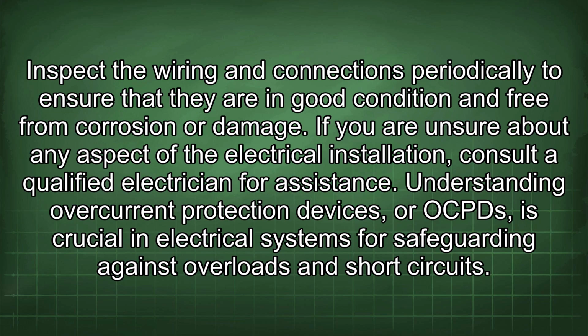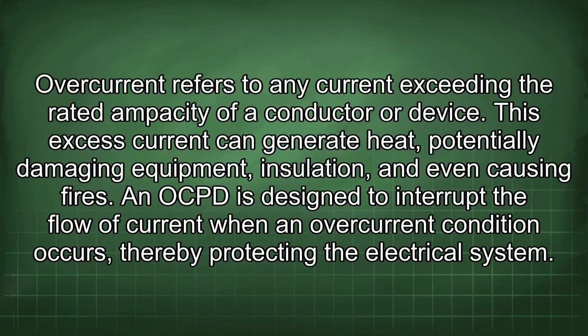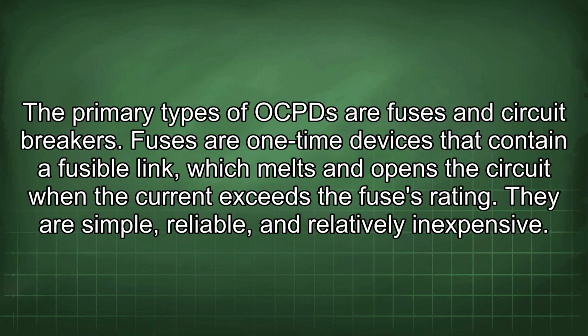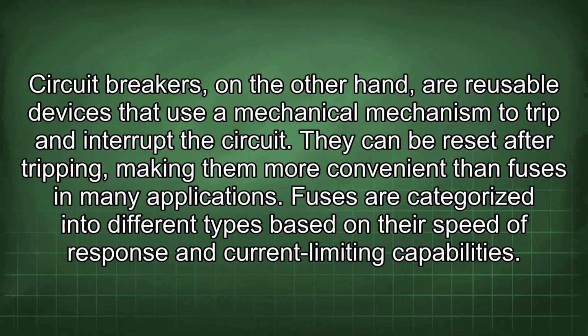Understanding overcurrent protection devices, or OCPDs, is crucial in electrical systems for safeguarding against overloads and short circuits. Overcurrent refers to any current exceeding the rated ampacity of a conductor or device. This excess current can generate heat, potentially damaging equipment, insulation, and even causing fires. An OCPD is designed to interrupt the flow of current when an overcurrent condition occurs, thereby protecting the electrical system. The primary types of OCPDs are fuses and circuit breakers. Fuses are one-time devices that contain a fusible link, which melts and opens the circuit when the current exceeds the fuse's rating. They are simple, reliable, and relatively inexpensive. Circuit breakers, on the other hand, are reusable devices that use a mechanical mechanism to trip and interrupt the circuit. They can be reset after tripping, making them more convenient than fuses in many applications.